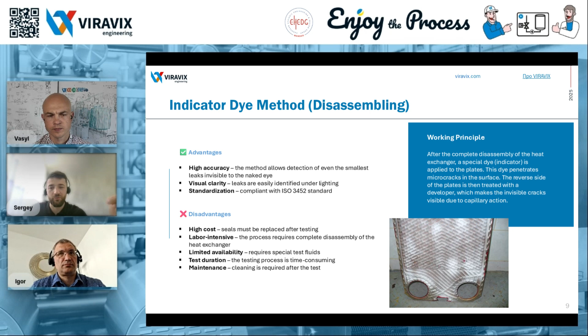So, the heat exchanger is also disassembled, and a special dye is applied. Then, the plates are dried for 20 to 30 minutes, and after drying, a UV lamp is directed at the painted side of the plate. At the damaged areas, spots appear that glow under ultraviolet light. So, the image shows an example of what it looks like, a clear visual representation and an indication of a crack. Both methods are identical, the only difference is the type of dye used. But in this case, a UV lamp is also required.